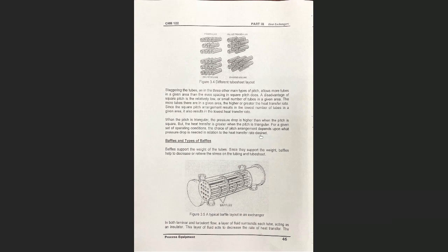الأول التيوبز أقل، تحتاج أنك تطول التيوبز، مثلا بدل ما يكون طولها 8 أمتار يصير طولها 10 أمتار. الإكستندر تحتل مساحة كبيرة داخل المصنع. جميل. أو أنك تضحي بالشيء الثاني اللي هو البريشر دروب، تختار اللاين تراينجلر مثلا لأنه يعطيك أكبر عدد من التيوبز، وبالتالي طول التيوب ما يكون كبير، يعني بدل ما يكون 10 يكون 7 متر فقط، لكن بتلاحظ أن في عندك انخفاض في الضغط.